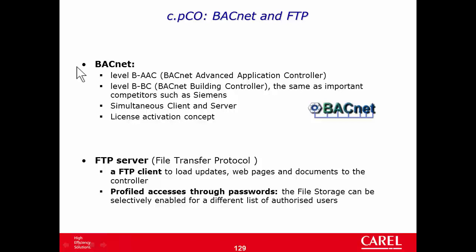BACnet protocol is natively supported with B-AAC and B-BC profiles. BACnet is a client-server protocol, similar to master-slave, and both can run simultaneously. In C-Design, you create just one line rather than separate master and slave lines as with Modbus or Carel. BACnet requires a license per controller — not for the editor. Contact your local sales representative for licensing details.